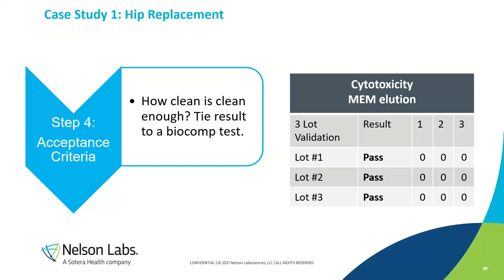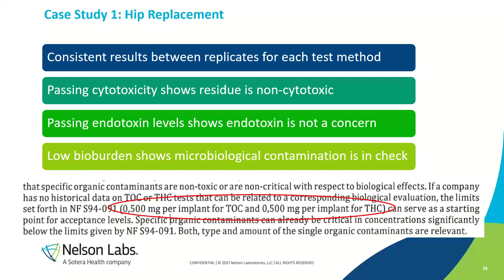And we saw, let's see, these are, to give you some context, if you're talking about 500 micrograms, you'd be looking at that middle column under the gravimetric if you're trying to make some kind of comparison between the ISO 19227 criteria. These look really good. These look reproducible, and they did spike recoveries for recovery efficiencies. Greater than 75% is considered successful, so they had 2 successful spike recoveries. It's pretty solid. I would consider these successful bioburden and bacterial endotoxin results. The endotoxins are all well below acceptance criteria. Bioburden acceptance criteria is one that might be established off of internal trend data, but there are a couple of other ways that can be used. So these look really good. There's a little bit of a spike on 10, but for a non-sterile device, that's not terrible. So here's a little highlight of the section in 19227 on that TOC and THC acceptance criteria.